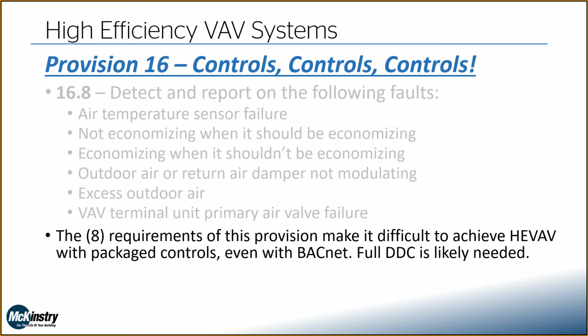This is a lot to do. This is a lot to ask your control system to do. And so again, this makes it really difficult to achieve high efficiency VAV with a packaged control system. Maybe even impossible. I'm not aware of any manufacturers who could meet all of these requirements. Even if we have a BACnet connection, you're still very likely dealing with some canned control logic that you're going to be stuck with. So you're very likely going to need a full-blown DDC system with custom sequences to achieve all of these provisions.